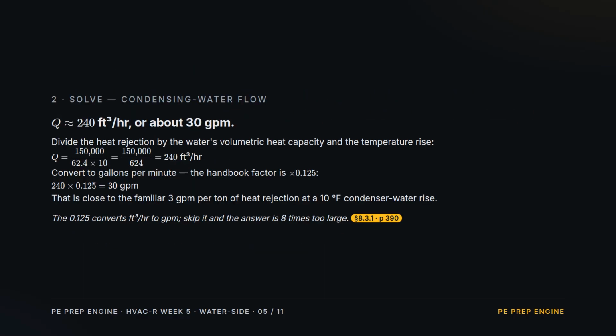Solve. Divide the heat rejection by the water's volumetric heat capacity and the 10-degree rise, and the flow is 240 cubic feet per hour. Multiply by the handbook's conversion factor, 0.125, and that is 30 GPM. Sanity check, that is close to the familiar 3 GPM per ton of heat rejection at a 10-degree condenser water rise.